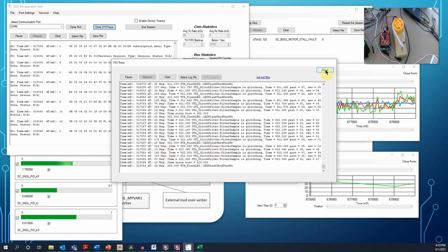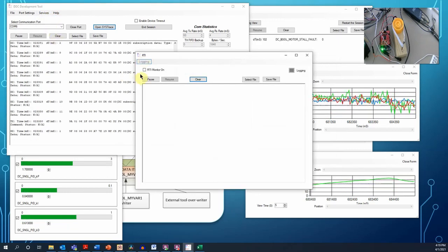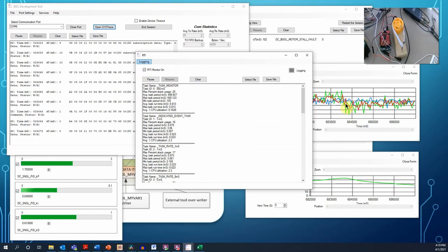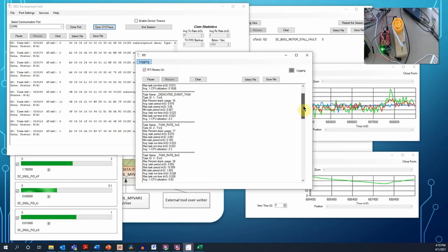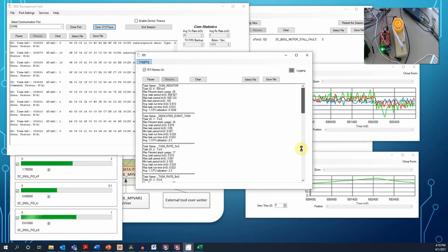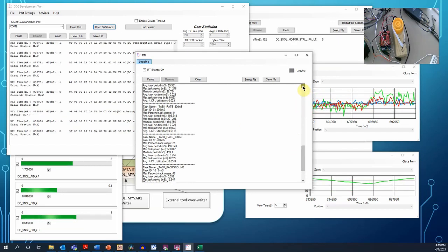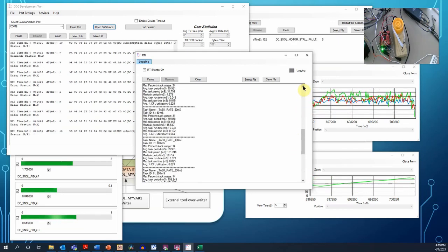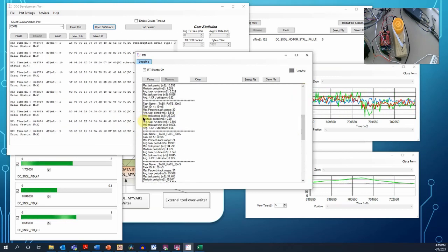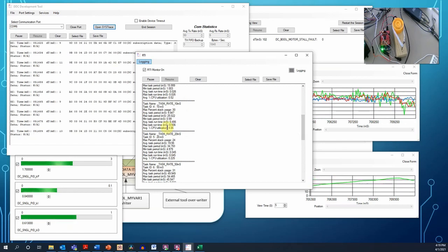And while we're here, we'll just go take a look at the Rti Stats. And we're on the 10 millisecond thread, or task. Here's the 200 millisecond. Let's get up to and find our 10 millisecond. All right, there's 10 milliseconds. So looks like we're using 30% of the stack. Periodic rate is 9.948. That's pretty close.